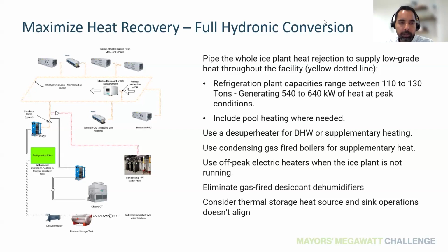See how you can tie that together to your ice plant, and also consider matching those loads closely. That's generally done by getting an hourly data profile of when your ice plant is working versus when you actually need heat in the building, because mapping those two out is critical in ensuring you have a heat source and a sink available and aligned.